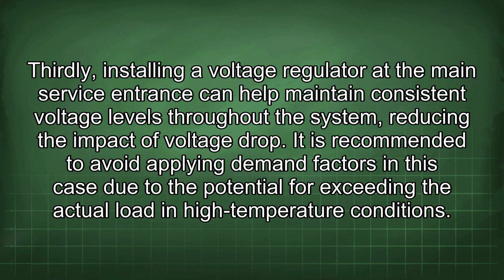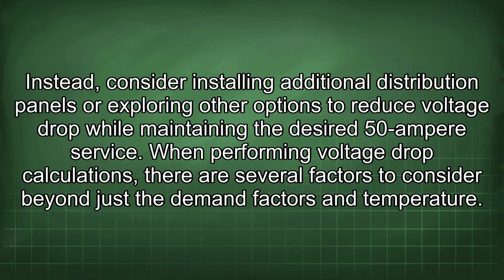It is recommended to avoid applying demand factors in this case due to the potential for exceeding the actual load in high temperature conditions. Instead, consider installing additional distribution panels or exploring other options to reduce voltage drop while maintaining the desired 50 ampere service.